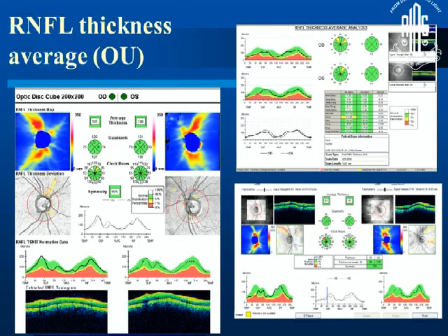So this is what the RNFL thickness is. The same patient on both. So this is pretty much similar to the Stratus. They've used the same circle. I'm showing this on the Cirrus OCT, but it's the same 3.4 millimeter circle that is used in all spectral domain OCTs, because that was what was found to be the most reproducible in the Stratus OCT.